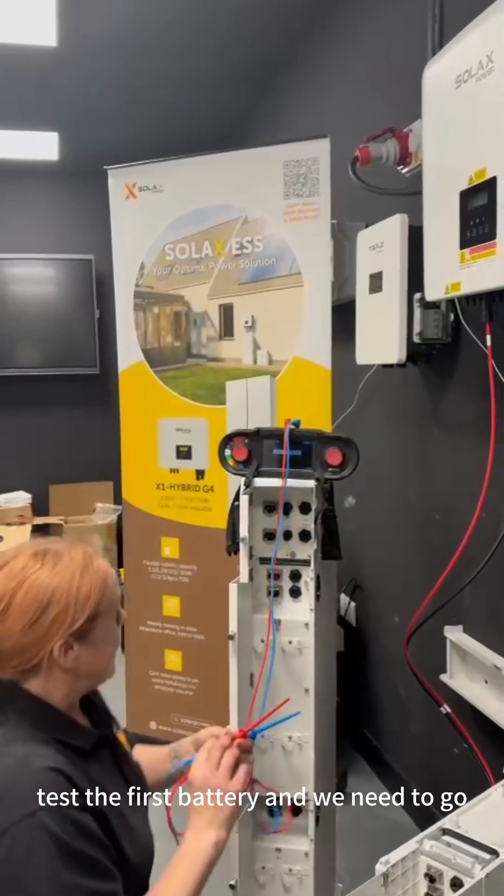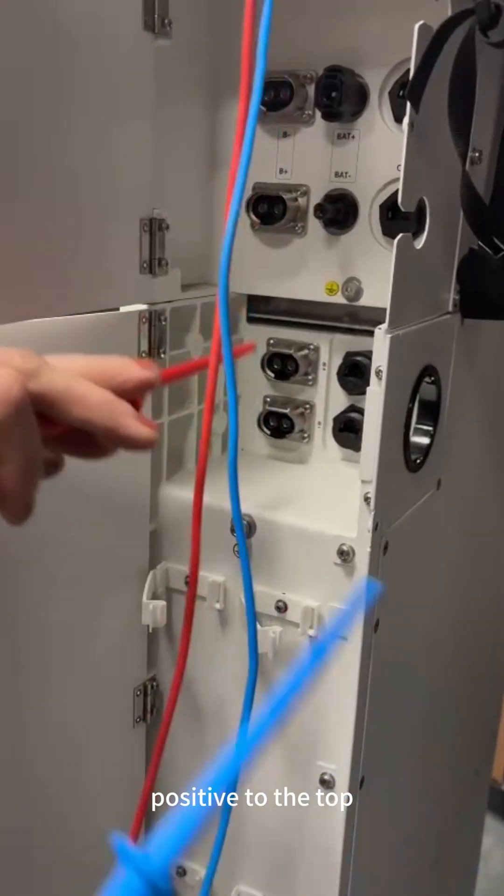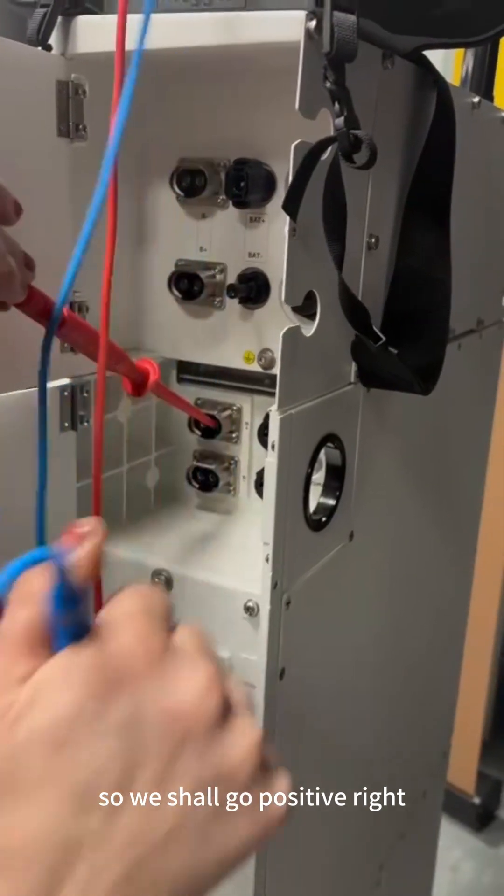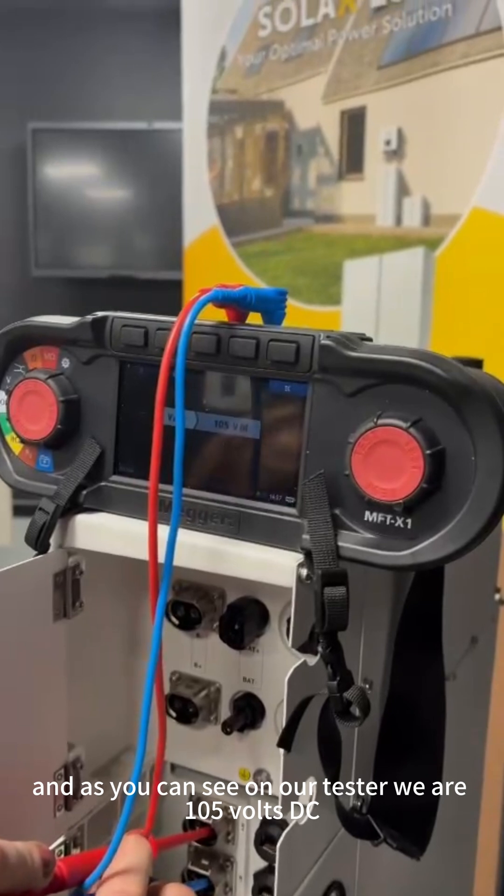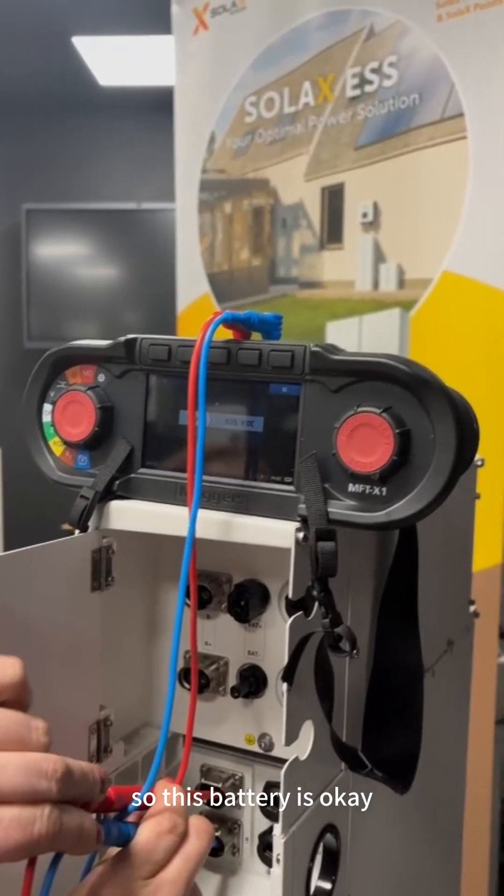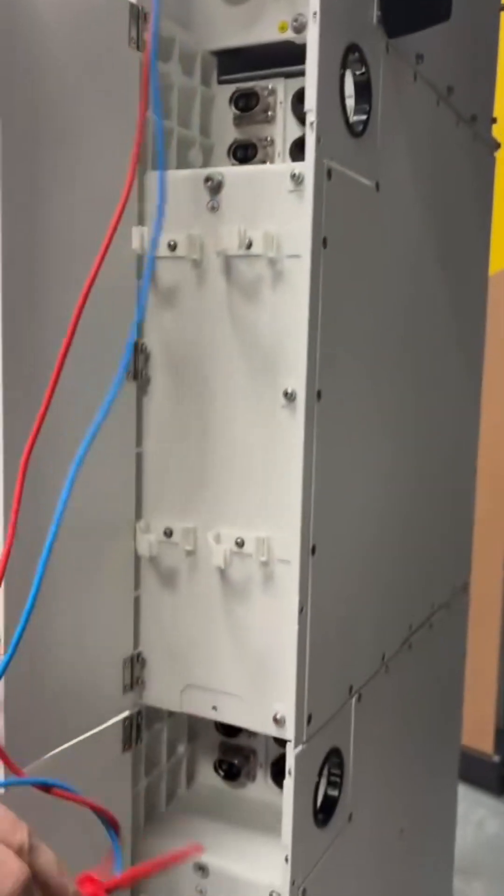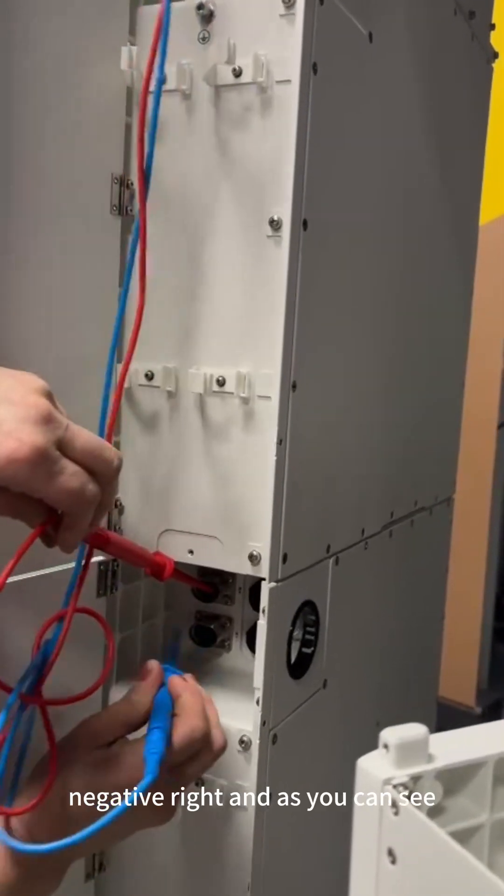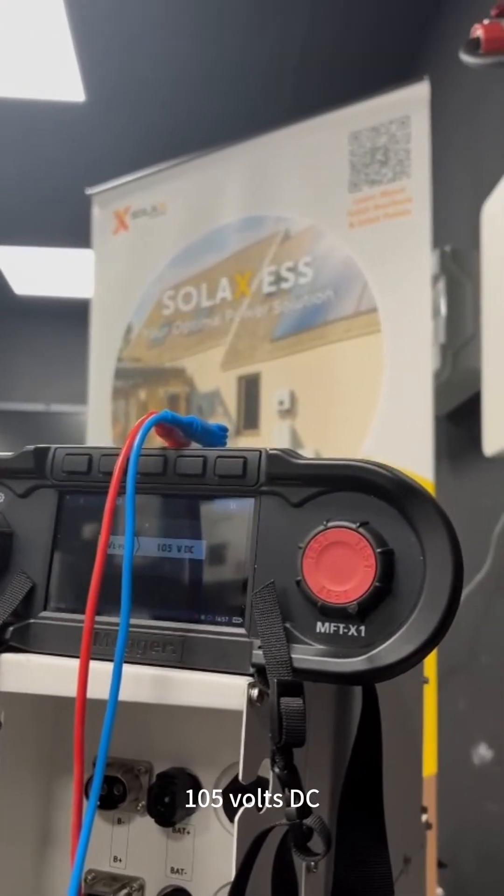We're going to test the first battery and we need to go positive to the top, negative to the bottom on the right hand side. So we shall go positive right, negative right. And as you can see on our tester, we are 105 volts DC. So this battery is OK. We'll test the next battery. Positive right, negative right. 105 volts DC.